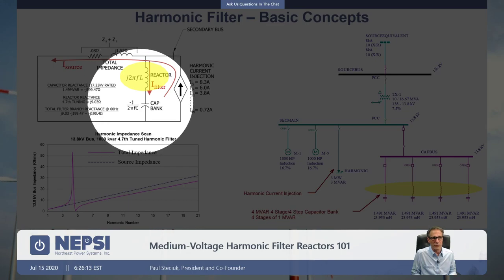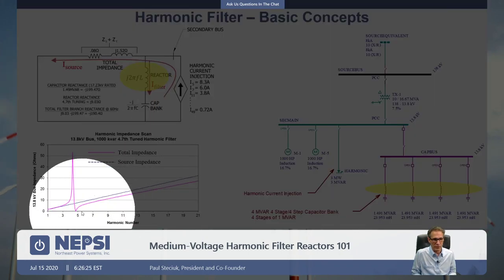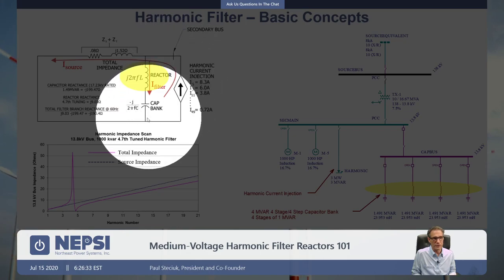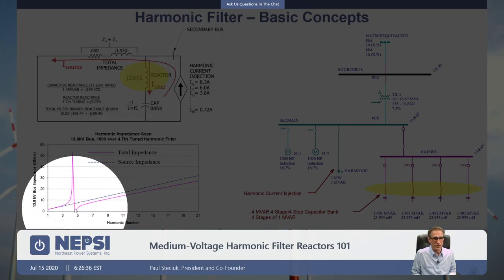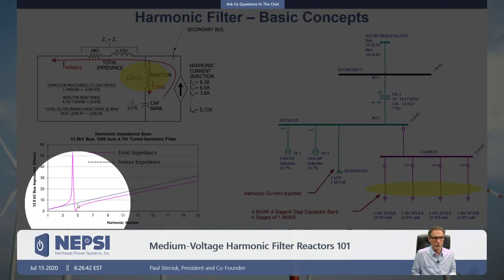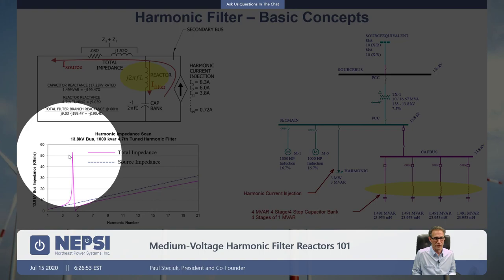When you have a capacitor bank, it causes resonance in the system. One of the key reasons you add a reactor to a capacitor bank is to tune it to a certain frequency. You can see on the lower left impedance scan the driving point impedance as seen from a harmonic-producing device. We're tuned at about the 4.7 harmonic here. All capacitor banks create resonances — even harmonic filters do — but harmonic filters control the resonant point.